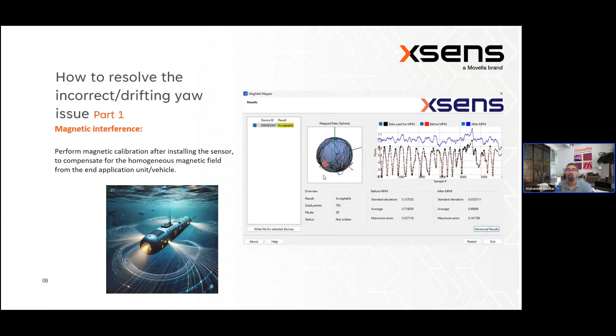Here you can see the after-calibration results. Basically, this is the before calibration, and this blue line is the after-calibration result. Essentially, what we are looking at here is the norm data. After an acceptable and good magnetic calibration, you should see that your norm is very constant at around the value 1. So this is what it's representing.